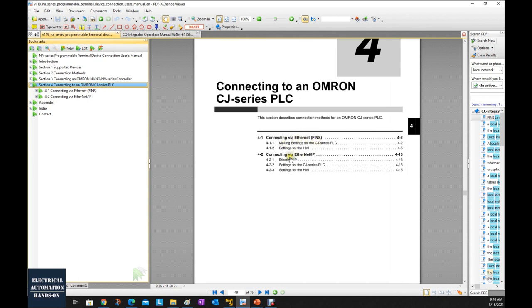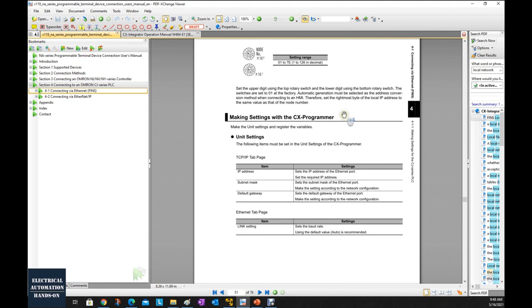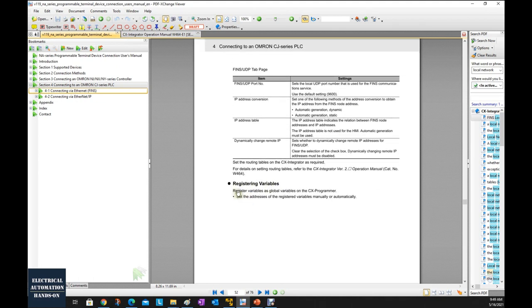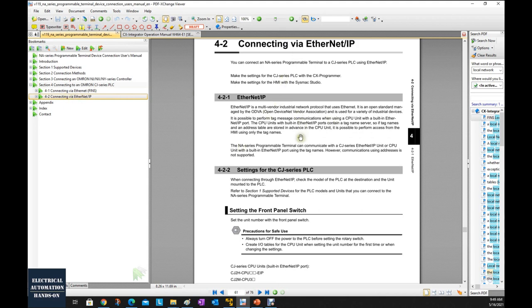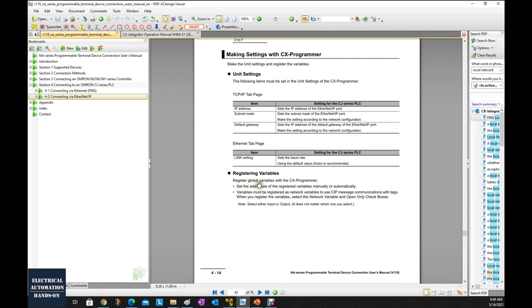The manual covers connecting with Ethernet FINS and connecting with EtherNet/IP. However, the limitation of this manual is that it only explains the HMI side — it doesn't explain the PLC side setup. The key difference between these two connections is this: for the FINS connection, it shows 'register variables as global variables on CX Programmer,' while for the EtherNet/IP connection, the variables must be registered as network variables to use CIP message communication with tags.